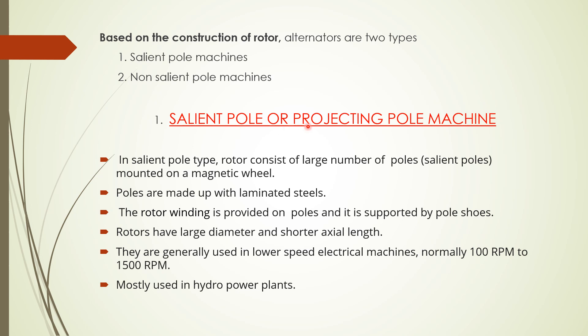The first type is salient pole machines, also known as projecting pole type machines. In salient pole machines the rotor consists of a large number of poles compared with non-salient pole machines, and they are mounted on a magnetic wheel structure which forms the rotor. The poles are made up of laminated steel in order to reduce eddy current losses, and the rotor winding is provided on the poles, supported by the pole shoes.